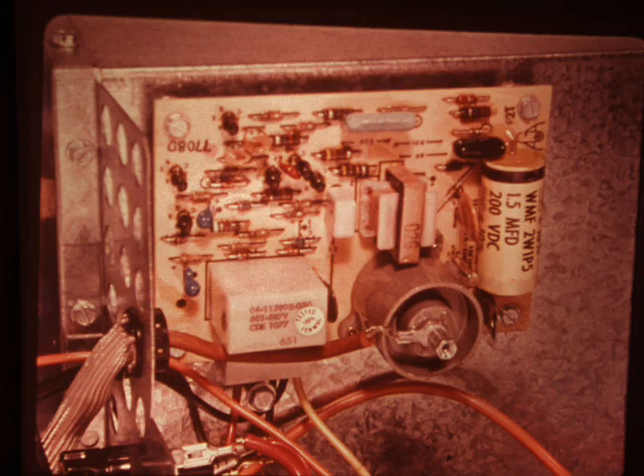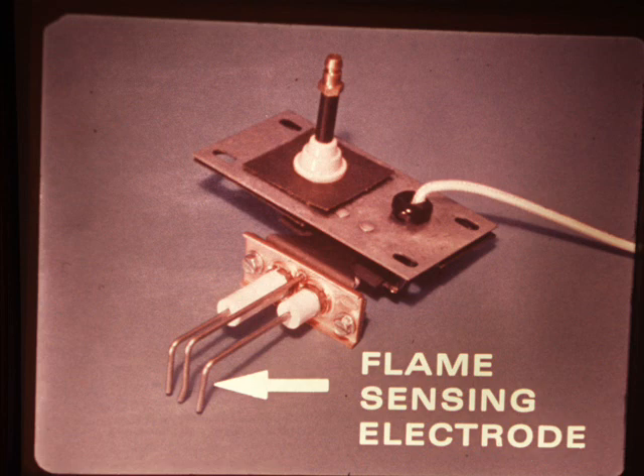The control module, also called an igniter board, develops the high voltage current for spark ignition and controls current flow to the gas solenoid valve. During the furnace start cycle, if a flame is not established within 15 seconds, the control module will close the solenoid valve. If the flame should go out during normal operation, the control module will provide one retry for ignition, then close the solenoid valve. The spark for ignition occurs between the spark and ground electrodes of the igniter assembly. The flame-sensing electrode detects the presence or absence of a burner flame, sending a microamp current signal to the control module.